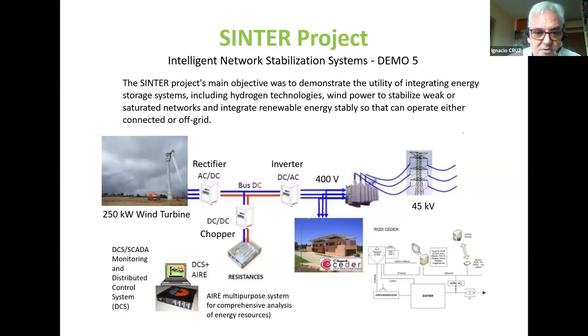The idea was to integrate this wind turbine, operating in a weak grid, limiting the surplus energy with a chopper and dump loads just in case. So a special control system was developed, a monitoring and distributed control system that was able to operate the wind turbine without trouble, even in situations with very limited grid parameters.